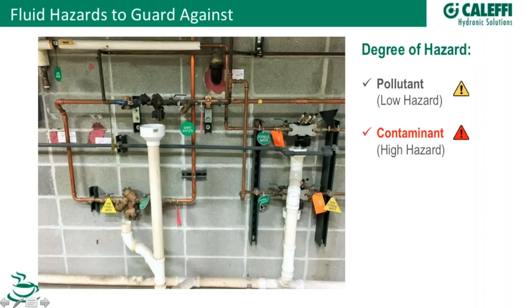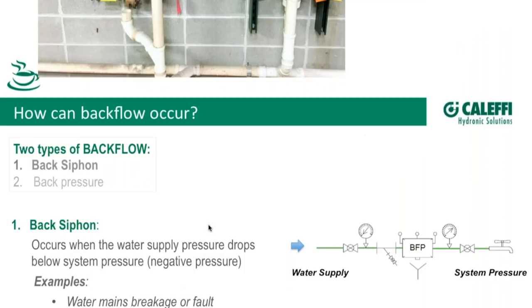Labeling and tagging is very important to tell everybody — mechanics, plumbers, and facility staff — what's going on with this water line before they assume it can be taken to any other equipment, especially for drinking or coffee. Green indicates the safe side — the international safe color. On piping on a ceiling, about every 25 feet you may just have a 6-inch green band. Labeling and tagging is addressed differently by different inspectors and authorities having jurisdiction, but typically every 20 to 25 feet, you want it color-coded, and if it goes through a wall, identify it again. Water quality to water safety changes.